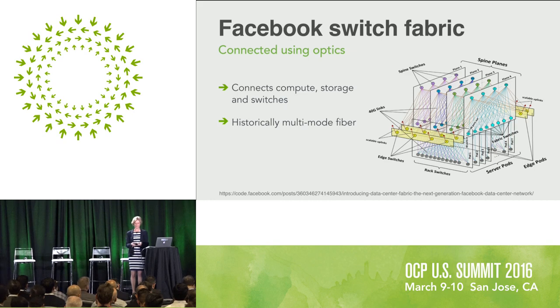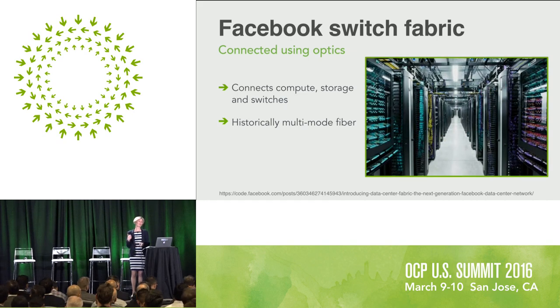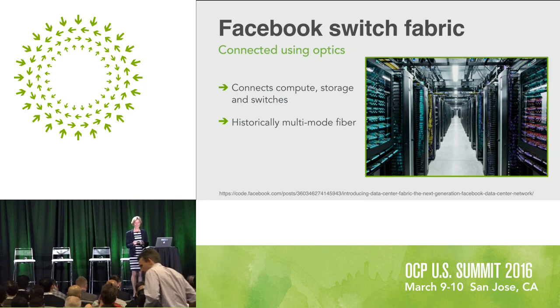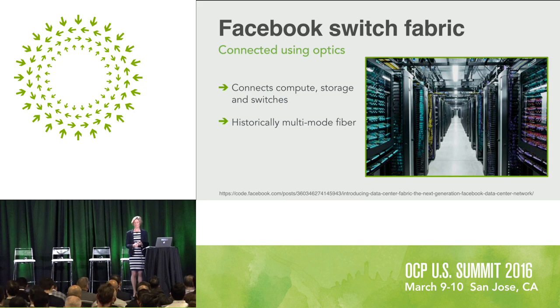This is a photograph taken inside one of our data centers — they all look the same on the inside. For those who know a little about optics, those color-coded cables are OM3 and OM4 multi-mode fiber. Historically our data centers have all been multi-mode fiber starting at 10 gig and then 40 gig, which was adequate for the distances required. But that's changing as we move to 100 gig and look at 400 gig and terabits per second — multi-mode fiber won't be sustainable.